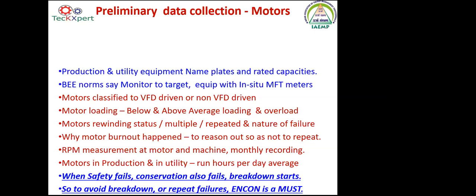The motor loading in the given industry, all these inputs are available to you. You just put them in different formats. All the values may be the same, but the formats may be different. For the motor loading, look at all the motors: those with loading less than 40%, which is under loading, average loading, where it is around 60 to 80%, and overloading. These inputs will show whether the motor needs a replacement, or whether it is due to excess load, or there is an unbalance in current which is causing the motor loading to be abnormal.